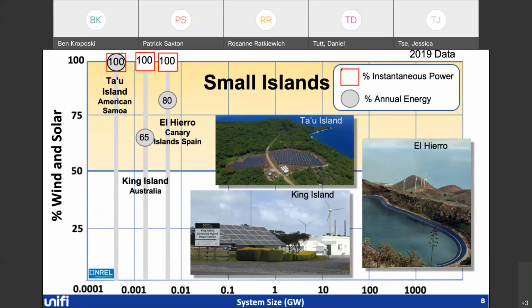Right, this red square is the instantaneous level, and what that means is at any particular point in time, it's going to be at that amount of wind or solar. But that could be 5 minutes, could be an hour. Doesn't have to be that long. And then the annual energy is over the entire year. So we know on small island power systems how to run these grids with very high levels of wind and solar. This little picture here in the middle is Tau Island in American Samoa. It runs a 100% solar system.